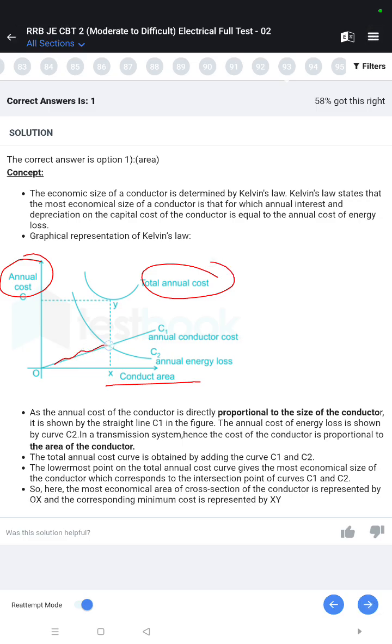Look at the graph between conductor area and annual cost. Total annual cost, C1 annual conductor cost, C2 annual energy loss, Y. As the annual cost of the conductor is directly proportional to the size of the conductor, it is shown by the straight line C1 in the figure. The annual cost of energy loss is shown by curve C2. In a transmission system, the cost of the conductor is proportional to the area of the conductor.